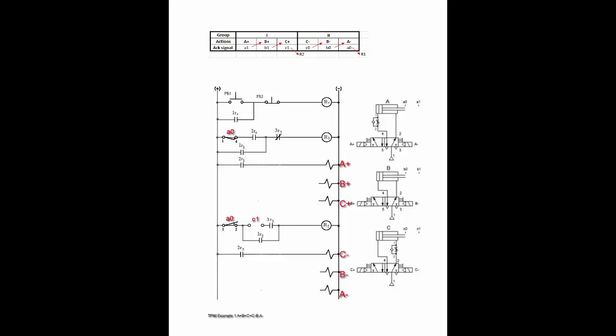Let us look at all the actions in group 1 under the control of group control relay R1. When R1 turns on, contact 2R1 is closed. Since A plus is the first action in this group, A plus is activated immediately without going through any limit switch. When A plus is completed, A1 is activated. A1 triggers B plus. When B plus is completed, B1 is activated. B1 triggers C plus. When C plus is completed, C1 is activated. Since C plus is the last action in this group, C1 triggers the next group control relay, R2.